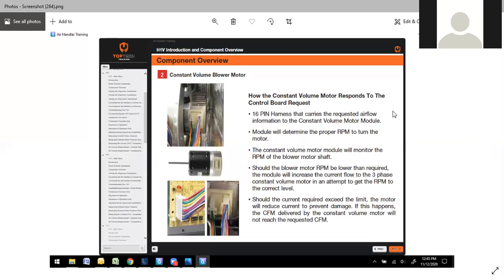How the constant volume motor responds to the control board request: the 16-pin harness carries the requested airflow information to the motor module. The module will determine the proper RPM and monitor the RPM of the blower motor shaft. Should the blower motor RPM be lower than required, the module will increase the current flow to the three-phase motor and attempt to get the RPM to the correct level. Should the current required exceed the limit, the motor will reduce current to prevent damage. If this happens, the CFM delivered by the constant volume motor will not reach the requested CFM. In some cases, they'll actually slow down to protect themselves.